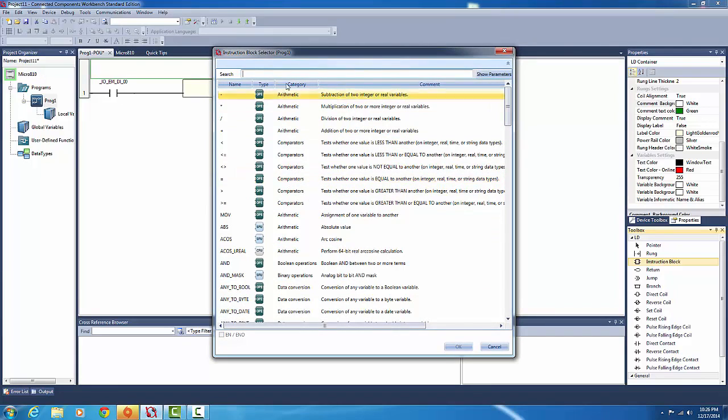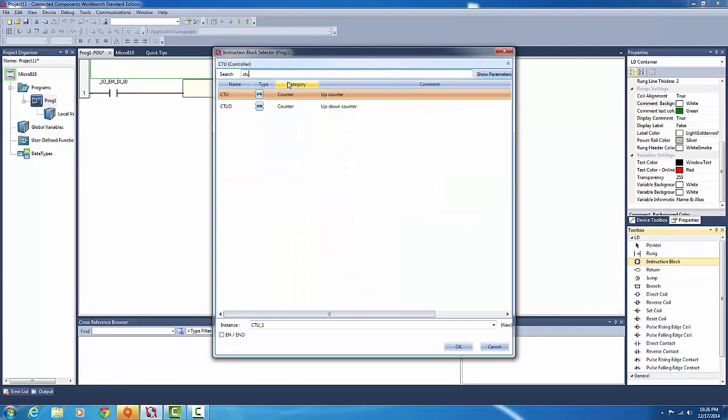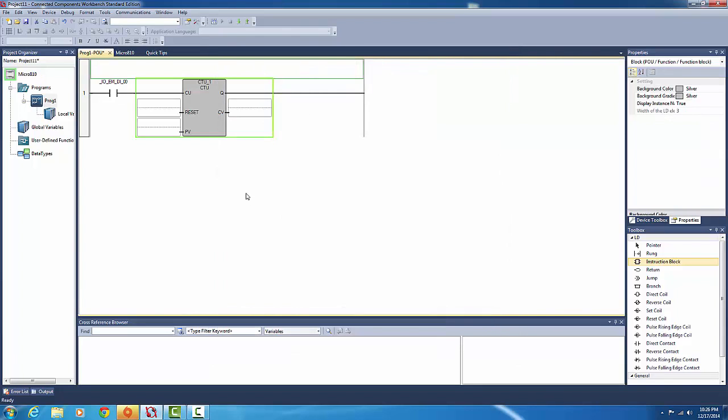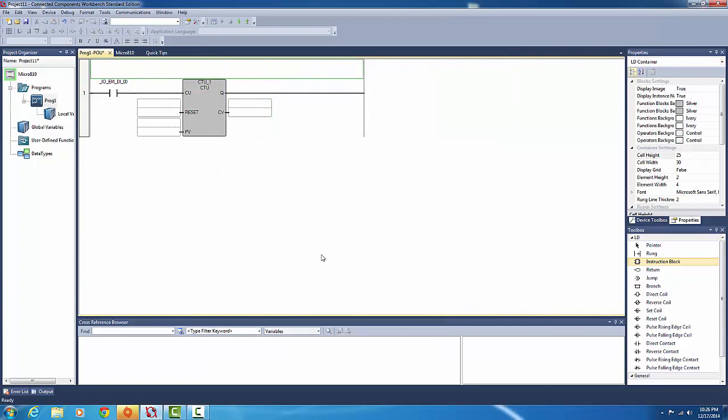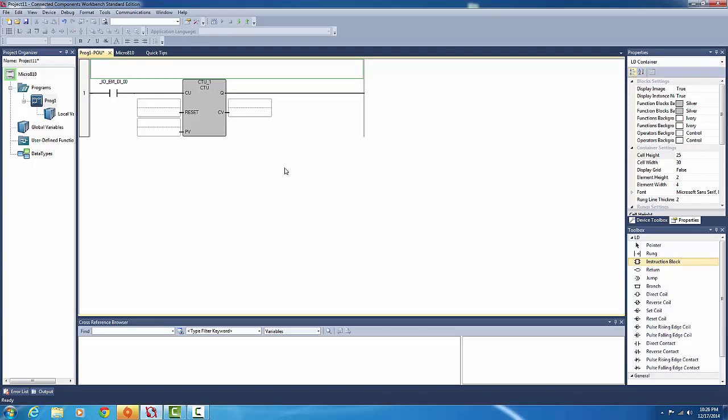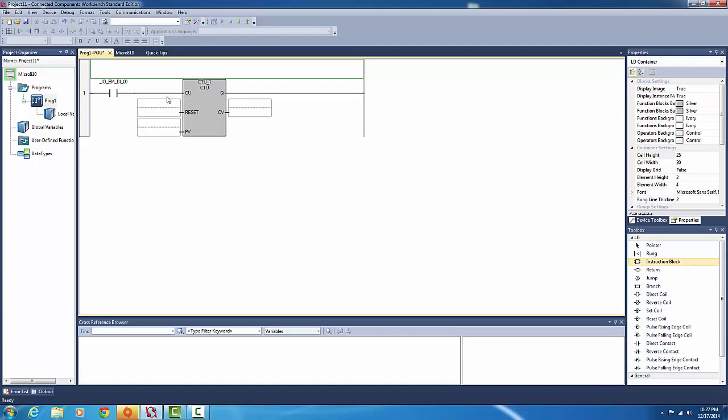Okay, and then we want to add our count-up timer. Right, CTU, that's short for up counter. So here we've got three variables: the current value, which we don't touch—it always starts at zero—the preset value where it needs to reach for this contact to close, and the reset button.